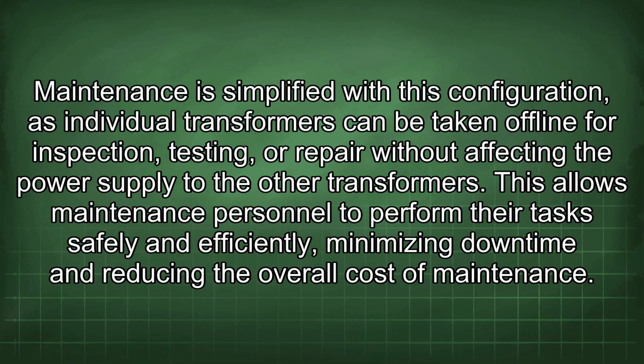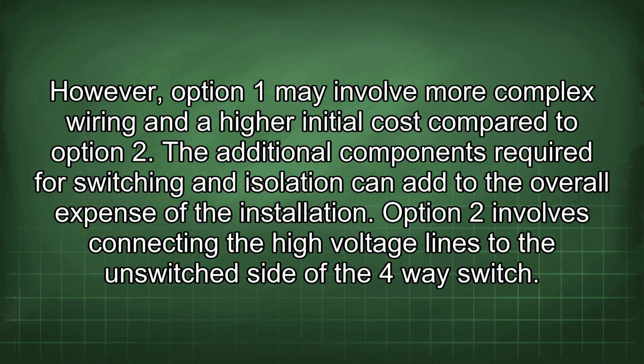Maintenance is simplified with this configuration, as individual transformers can be taken offline for inspection, testing, or repair without affecting the power supply to the other transformers. This allows maintenance personnel to perform their tasks safely and efficiently, minimizing downtime and reducing the overall cost of maintenance. However, Option 1 may involve more complex wiring and a higher initial cost compared to Option 2. The additional components required for switching and isolation can add to the overall expense of the installation.